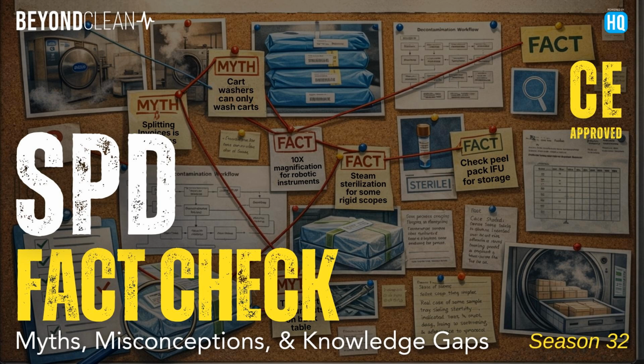There are different manufacturers who have different techniques to remove those deposits, and there are different manufacturers with different recommendations on how often you should. Obviously, we should be doing a visual inspection after every single reprocessing cycle, but let's assume it's after 20 uses in an autoclave or after 50. What's our next step? Because we're going to see those deposits.